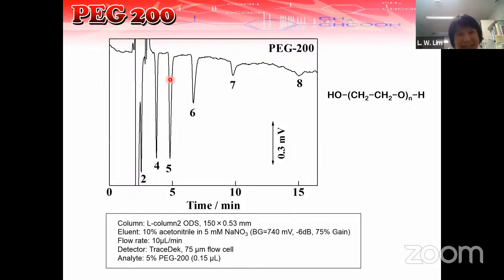Sometimes if you see some peaks lower and some peaks upper, that is how we modify the eluent to have a different selectivity. In other cases, if you are good at maintaining the background, you can actually have negative and positive peaks at the same time.